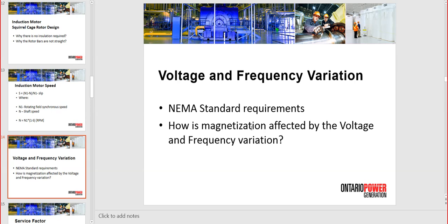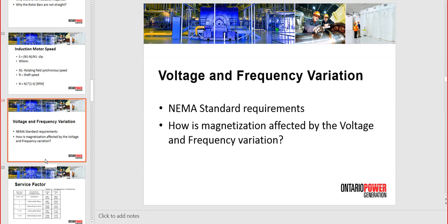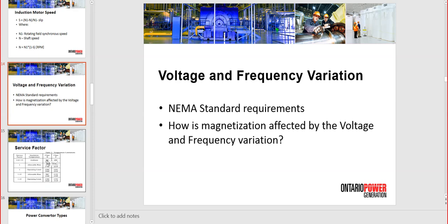Voltage and frequency variation. NEMA also tells you that a motor should be designed such that when you test the motor it is passing, so the three phase resistance should be within 5%, but it should accept variation of the three phase voltages, like plus or minus 10% in voltage or plus or minus 1 Hertz in the power supply, without affecting the performance of the motor. After that, yes, it is derated with the square of the voltage. So a lower voltage is not linear. If you apply half voltage to a motor at 60 Hertz, you will develop only a quarter of the torque, because it is proportional to the squared voltage. Okay, so keep that in mind. The torque is not linear with the voltage, it's proportional to the squared voltage.